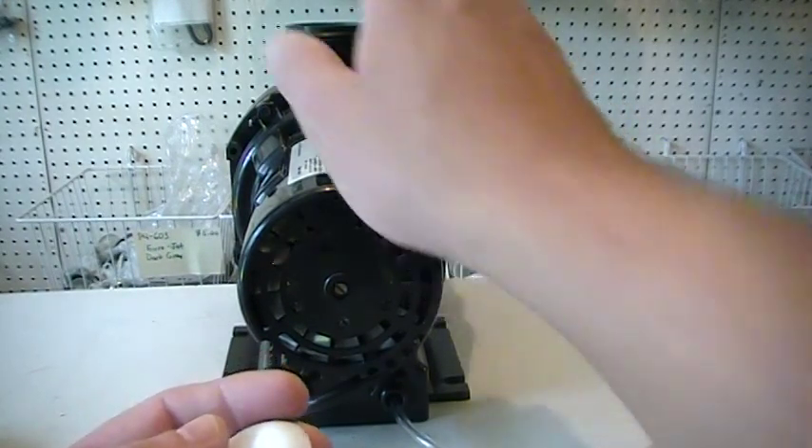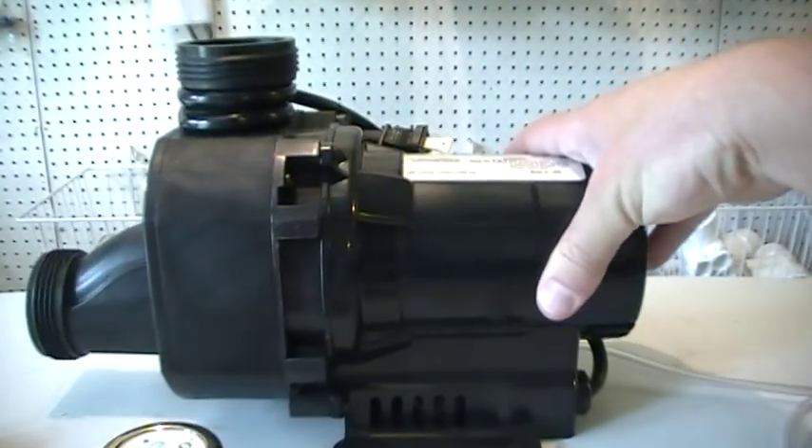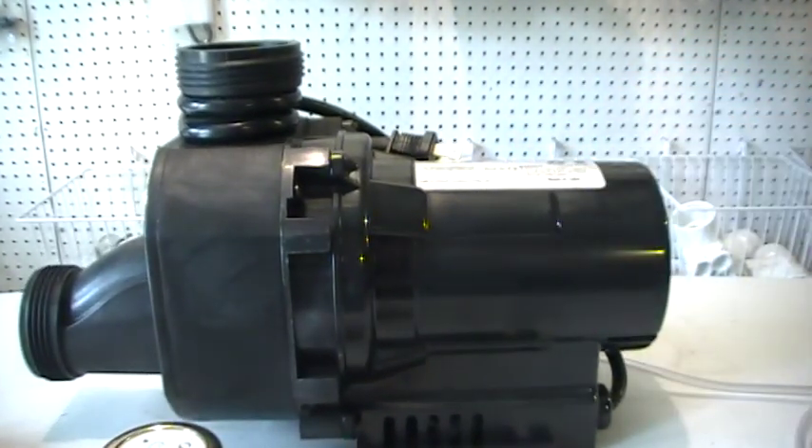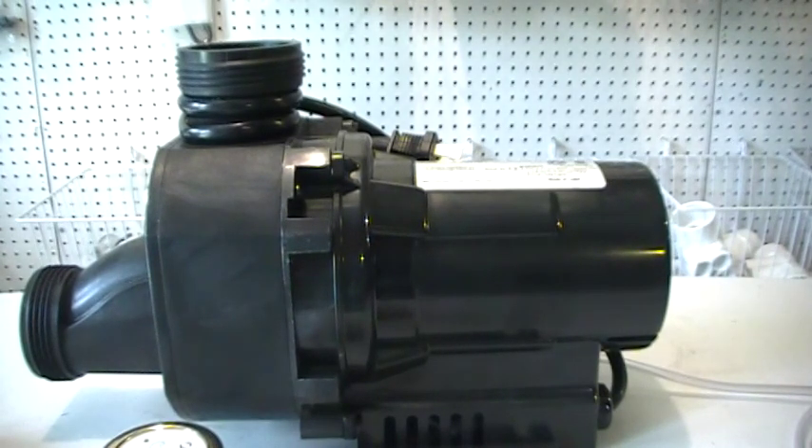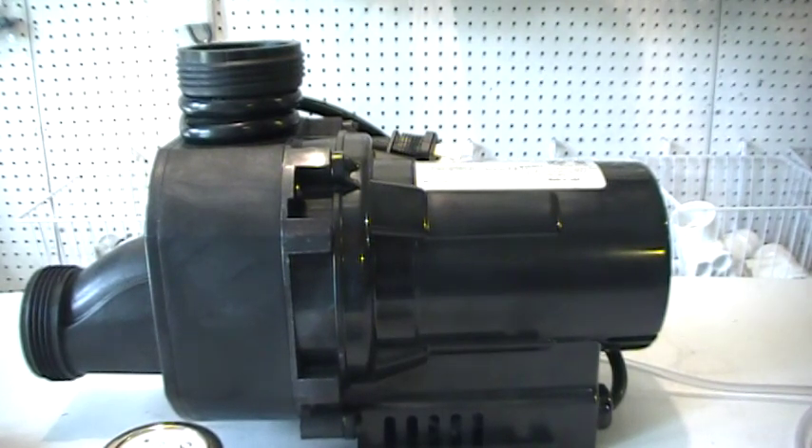This particular pump — you can use two pumps for this application as a replacement for the old ITT Marlow pumps. This one here is the NR4 A-C. It is a 12.5 amp pump and it will replace the one and a quarter horsepower pumps — the R100 VS and the R150 VS. If you have a smaller pump, three quarter horsepower, you will go with the NR2 A-C. Both of those links for these two pumps are in the description below this video.